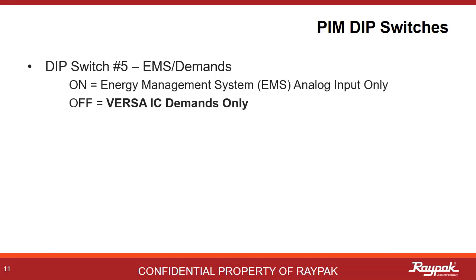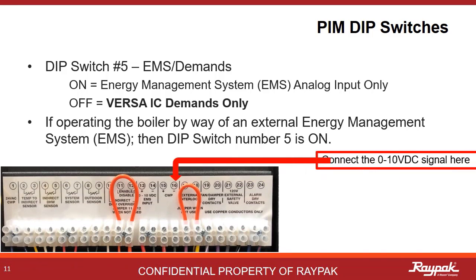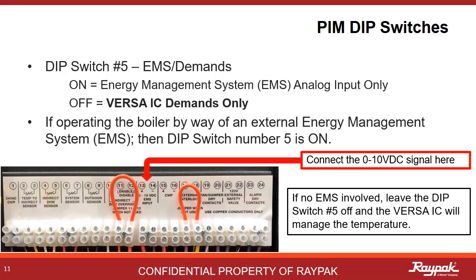PIM dip switch number five needs to be on to engage dip switches number two and number six, as they all support energy management systems. When driving the boiler from an external controller like an energy management system, also known as a building management system, turn on dip switch number five. The energy management system will connect up to ports 13 and 14 on the low voltage panel. If not driving from an energy management system, leave dip switch number five off and the Versa system will drive the boiler.